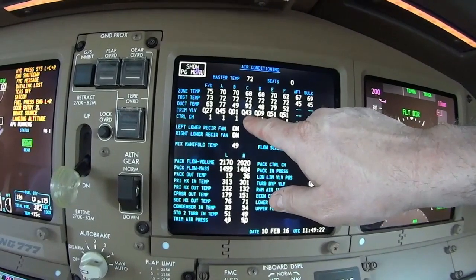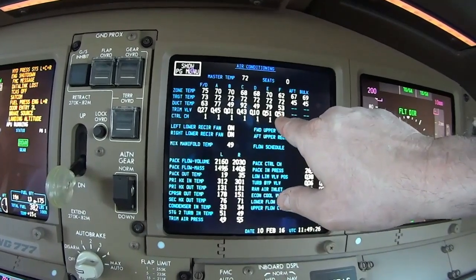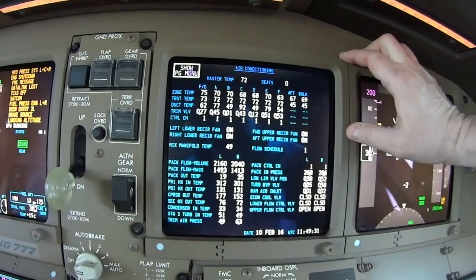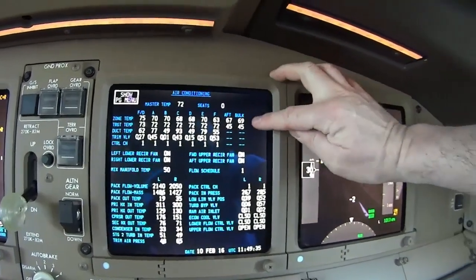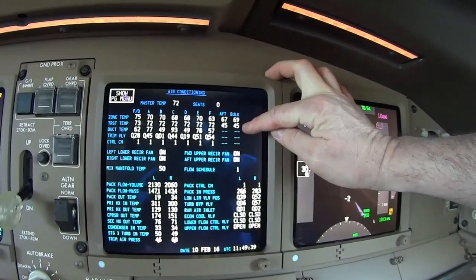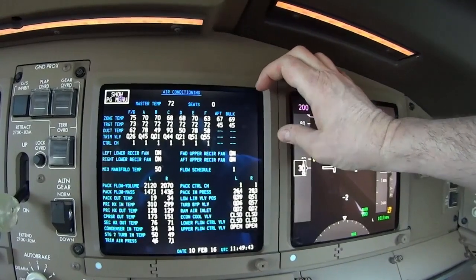And then these are dumping in different quantities of hot air to mix in with that 48 degree air. And these back here, they're controlled separately, and they'll just get dumped in to keep them at close to 45 degrees.